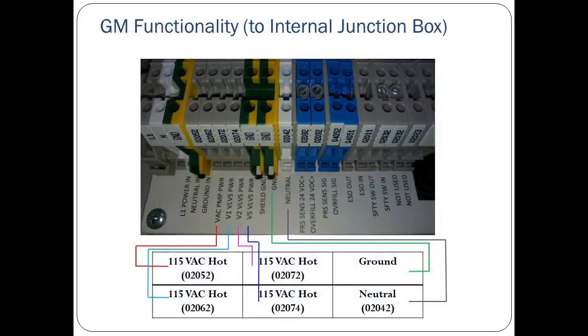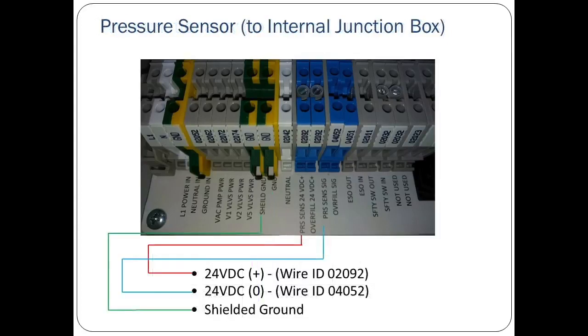Take a look at the terminal blocks inside the VST control panel. Highlighted here are the places where each of the 6 wires that are being run to the Green Machine internal junction box are to be terminated. Next are where the wires within the pressure sensor cable are to be terminated in the VST control panel. This cable should be pulled alongside the functional wires to the Green Machine internal junction box. And again, notice the ease in matching wires to the terminal blocks because of the identifiers.